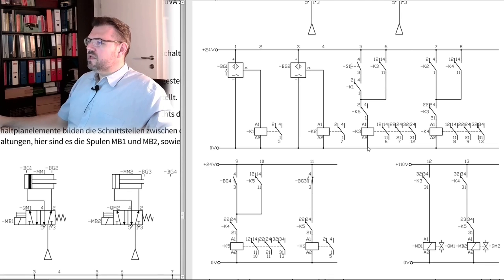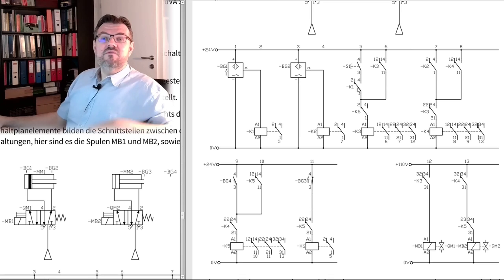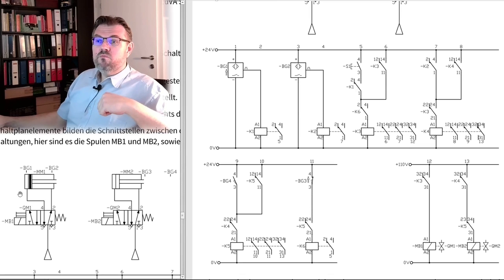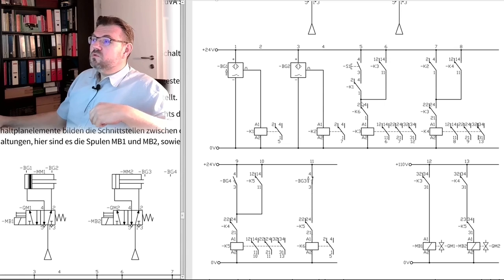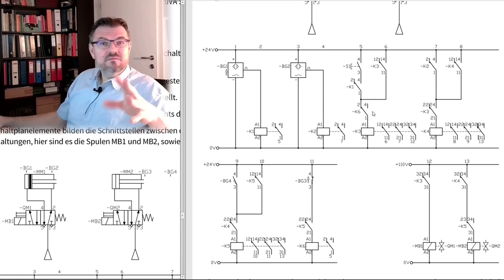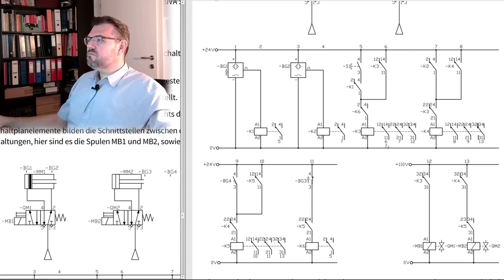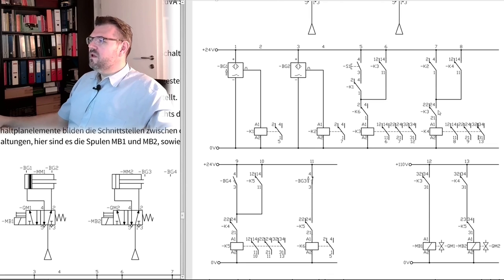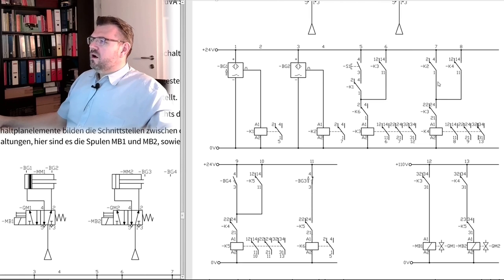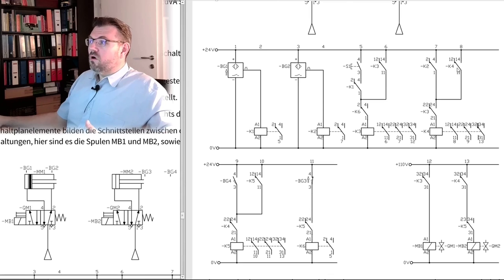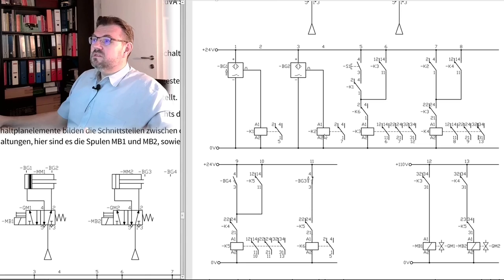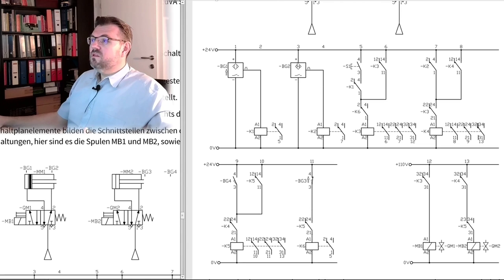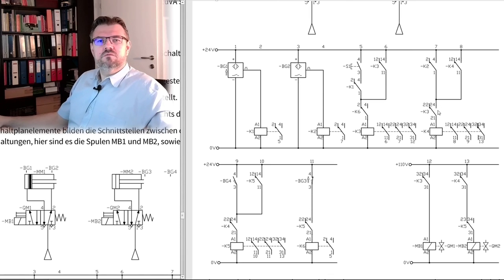K3 will stay on, for sure, even if I release the button. Or, even if the cylinder would travel outwards, and K1 is open, also then K3 is not going to be switched off. And then, in part number 7, K3 is closing. This will not change anything, because actually, K4 is for sure off, because K3 was open, so K4 was off, and K2, this is the limit switch, the outer limit switch of MM1, this is also open, so we will just prepare this, we will just close this. Right now, it has no effect.